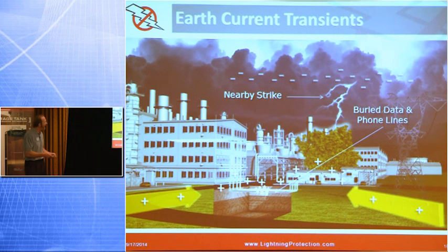So now we have a lightning strike in the vicinity, let's say to this tree, not even to the building itself. What has to happen? Now the earth surface, again, is working like a plate of a capacitor, holding that charge. Even though it's a rather poor semiconductor, it does hold that charge. And now that positive charge has to propagate, rush, flow very quickly to the point of termination in microseconds.